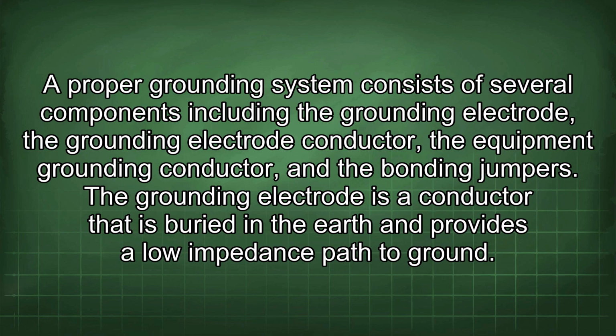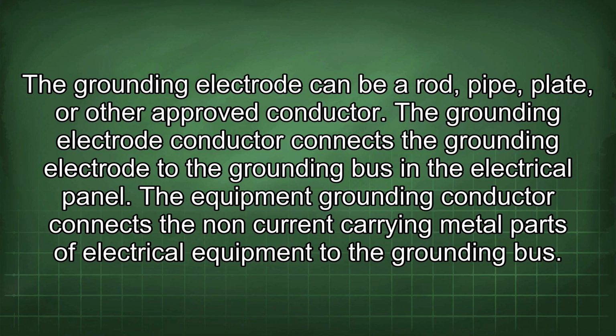A proper grounding system consists of several components, including the grounding electrode conductor, equipment grounding conductor, and the bonding jumpers. The grounding electrode is a conductor that is buried in the earth and provides a low impedance path to ground. The grounding electrode can be a rod, pipe, plate, or other approved conductor. The grounding electrode conductor connects the grounding electrode to the grounding bus in the electrical panel. The equipment grounding conductor connects the non-current carrying metal parts of electrical equipment to the grounding bus.